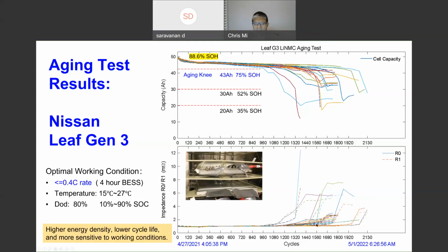From the bottom graph, you can see the impedance increased dramatically at the point they reach the aging knee, and it's not a simple percentage increase, it's many times increase. So our conclusion is that once this battery reaches the aging knee, it has to be retired. We cannot continue to use them because it's dangerous.